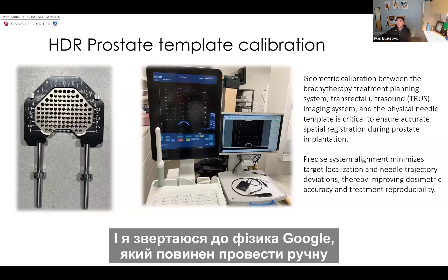There is a procedure in AAPM Task Group 128 on how to do additional quality assurance tests such as accuracy at different penetration depths, etc. And I refer the physicist who's supposed to perform the manual QA check to that document. So which catheters and markers should be used? We use ProGuide plastic needles because they are flexible, and in order to insert those needles, it is necessary to put inside a steel insert or an obturator that will allow for easy penetration or insertion of the needles. And all these needles should be properly QA'd.